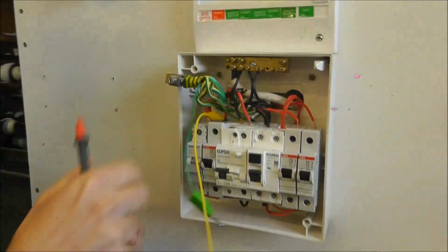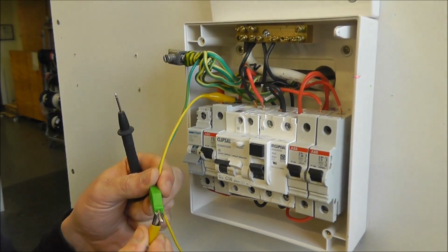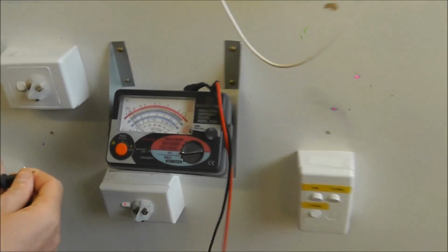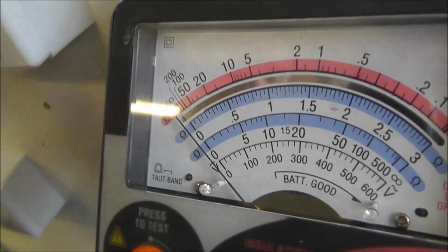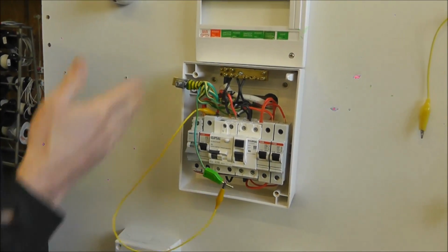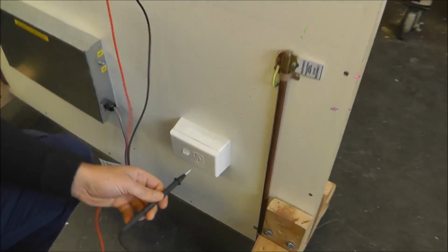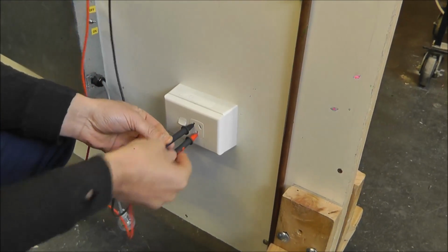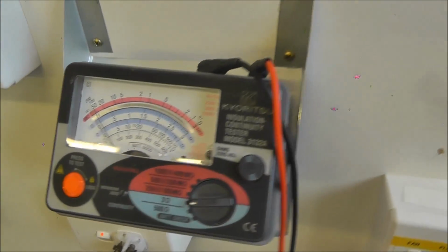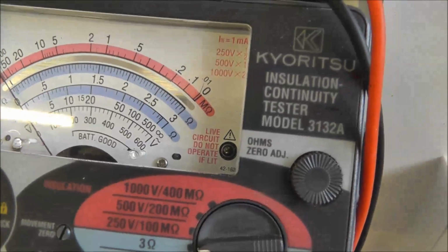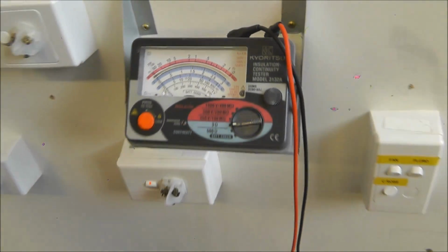So when I put this back on over here, I've allowed for the resistance of the lead. So if I go over here, that's going to be slightly above zero. Oh no, slightly below because it's got to come up. Yep. Okay? So I'm testing the active to earth loop. So I've got a connection up here, haven't I, Rossi? So therefore, if I get down here and go active to earth, turn the switch on, that is going to tell me my reading. 0.05, is it? 0.05. Yep, I'm happy with that.